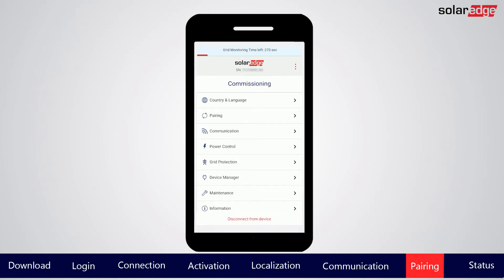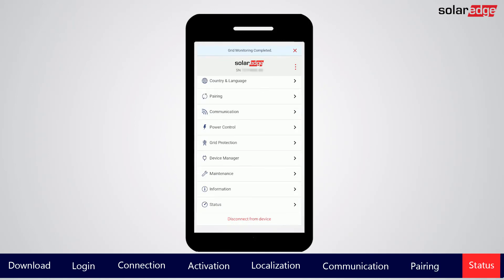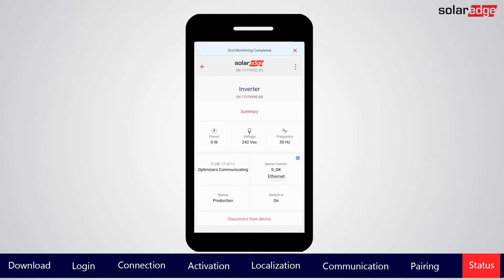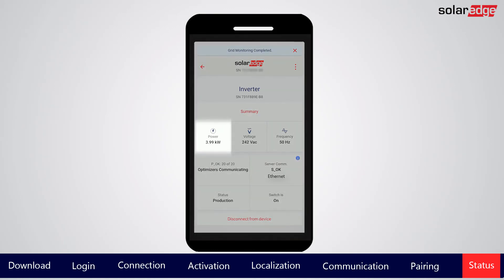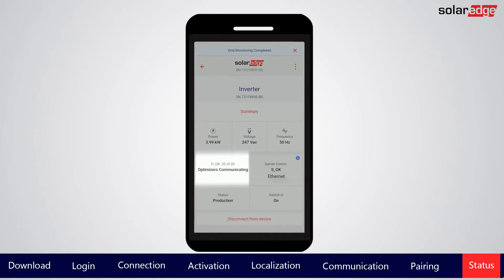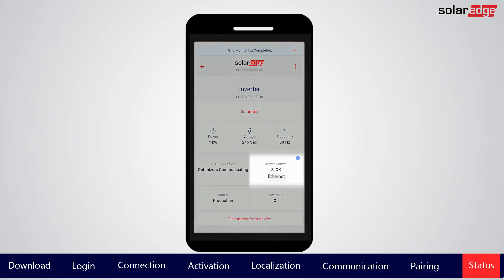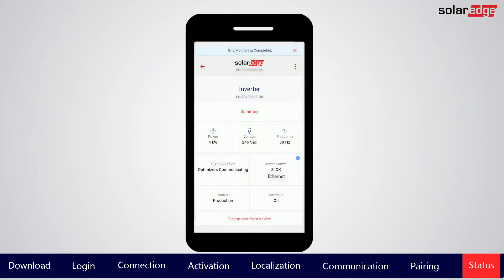Before producing power, the inverter will go through a 5-minute grid monitoring period. During this period, grid monitoring will be displayed at the top of the status screen. Let's go to the status screen to verify configuration and pairing. Verify that once grid monitoring is complete, you can see power increasing in the power box. Check to see if the number of power optimizers on the screen matches the number of power optimizers installed and connected to the inverter. Verify the connection to the monitoring platform — S_OK in the server communication box signifies a successful connection.